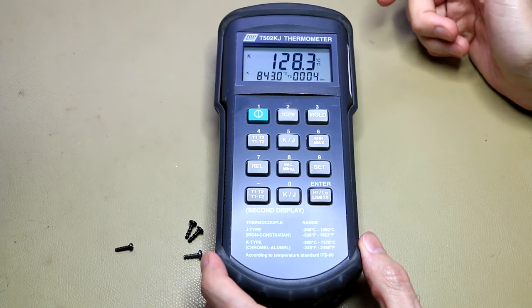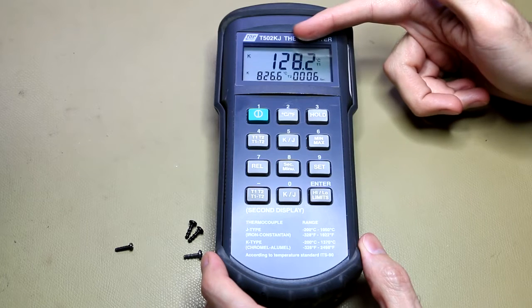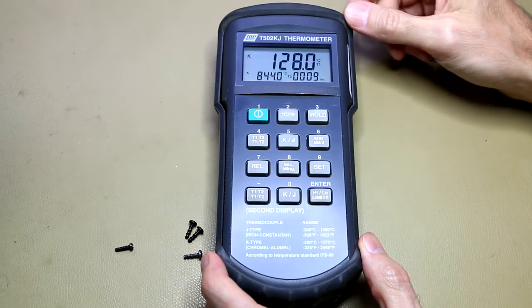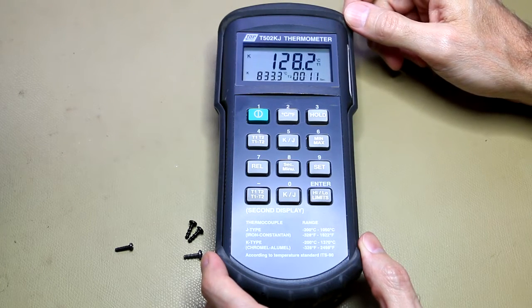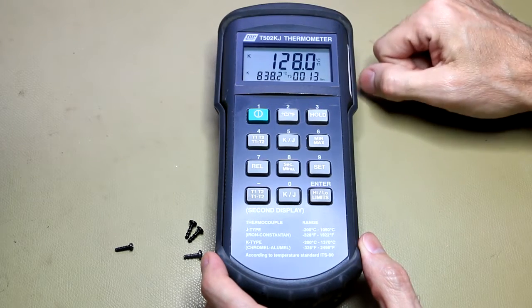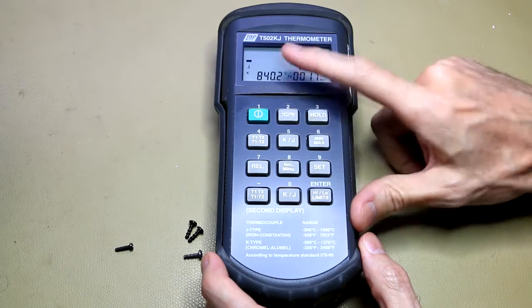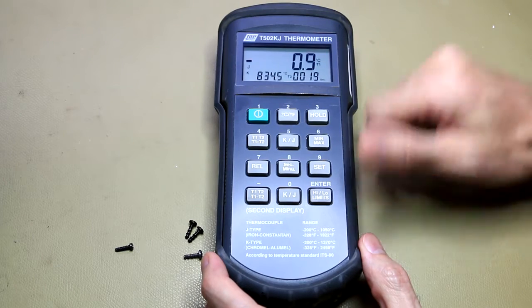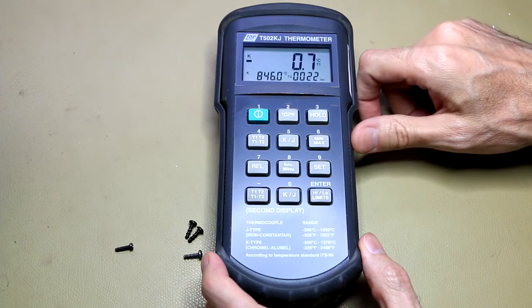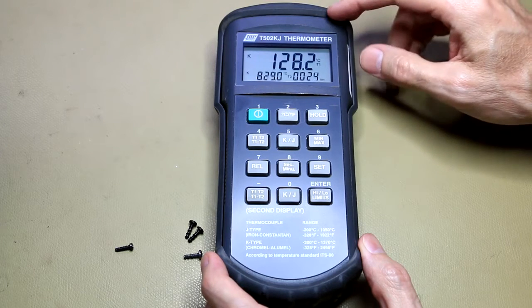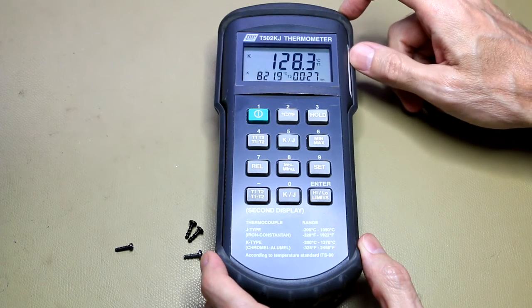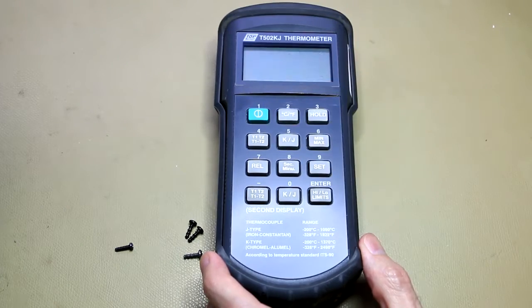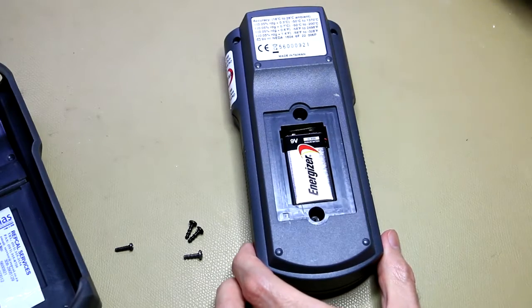completely erroneous temperatures: 128 degrees Celsius on one, 800 and something odd degrees Celsius on the other, and there are no probes connected. If I switch to J-type you see it completely changes, also to completely erroneous readings. So I think let's open this thermometer up and see if we can determine what exactly the problem is.